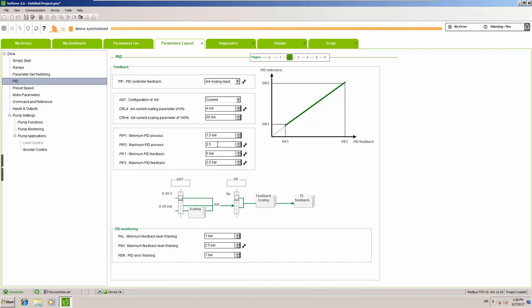We can also set up our process units — technically this is your setpoint setup. These are the minimum and maximum values you can set for your pressure setpoint. We will put 0 and 2.5 bars. For warning levels, we disable them for this application and leave the PID error warning at 1 bar, which is enough for our application without tripping it.